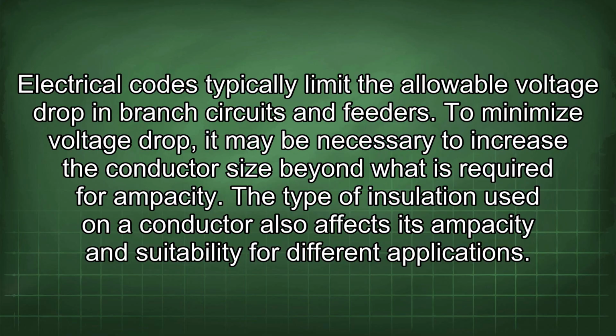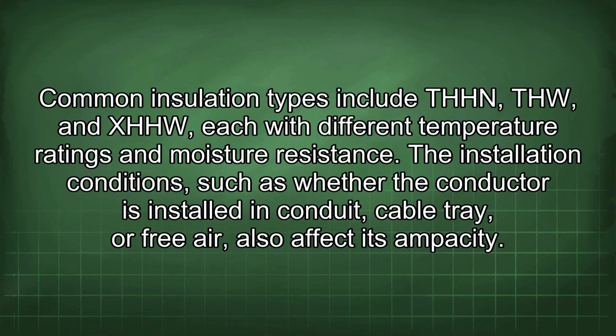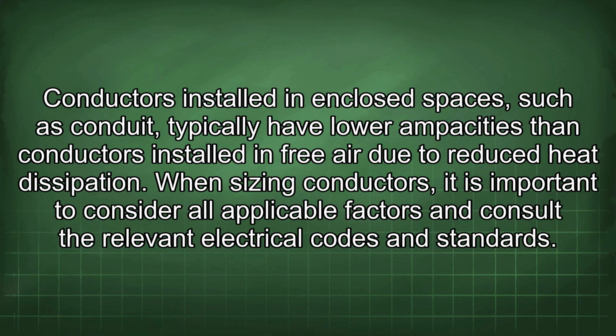The type of insulation used on a conductor also affects its ampacity and suitability for different applications. Common insulation types include THHN, THW, and XHHW, each with different temperature ratings and moisture resistance. The installation conditions, such as whether the conductor is installed in conduit, cable tray, or free air, also affect its ampacity. Conductors installed in enclosed spaces, such as conduit, typically have lower ampacities than conductors installed in free air due to reduced heat dissipation.